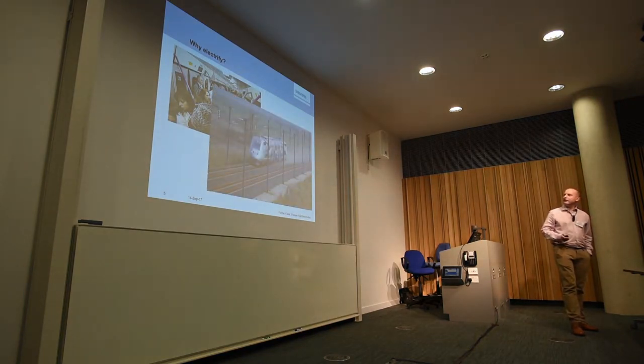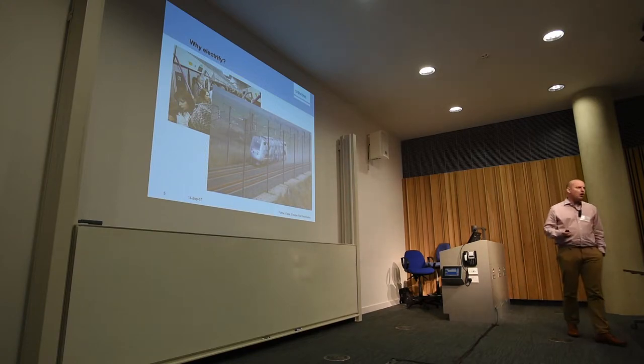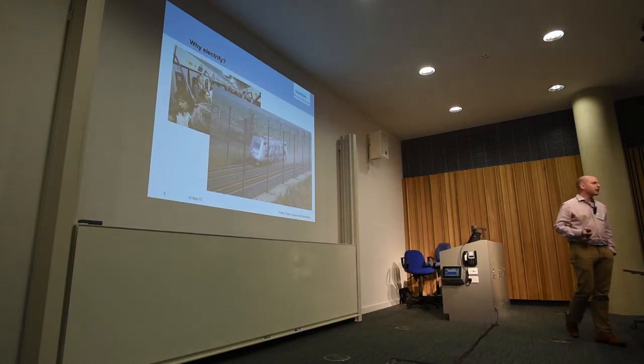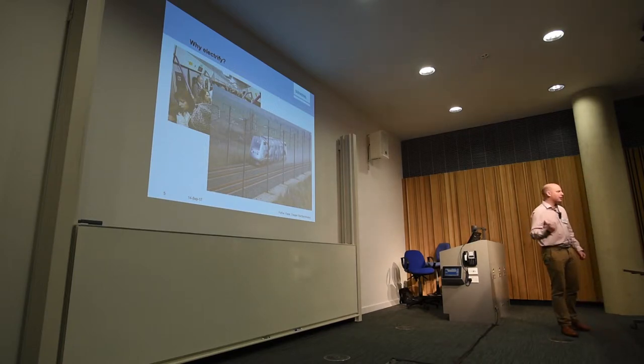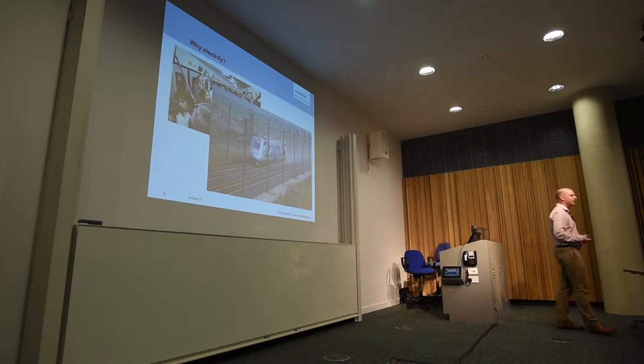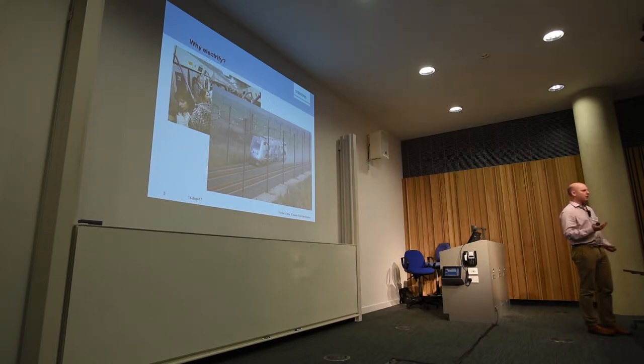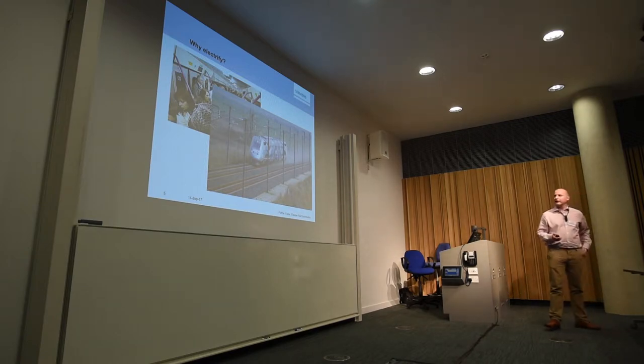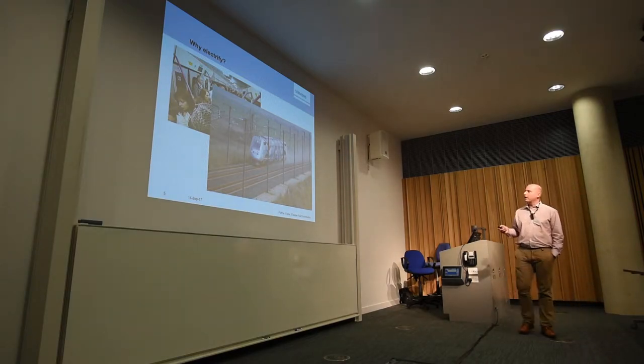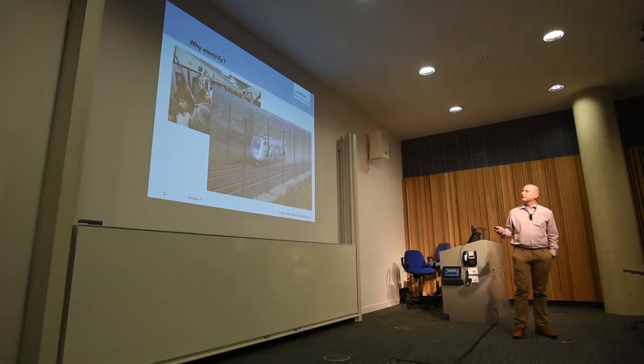One of the other main reasons is where you need very high power. You need high power for two reasons. All high-speed rail is electrified because you simply cannot get an economic diesel solution to deliver the types of power we're talking about. We're talking 15 to 20 megawatts with quite high continuous ratings as well, because the aerodynamic losses require continuous high power at those speeds.